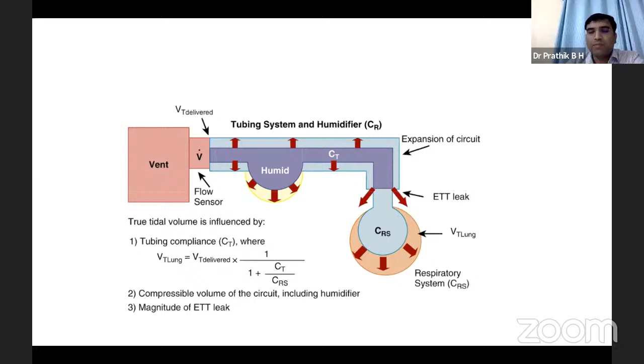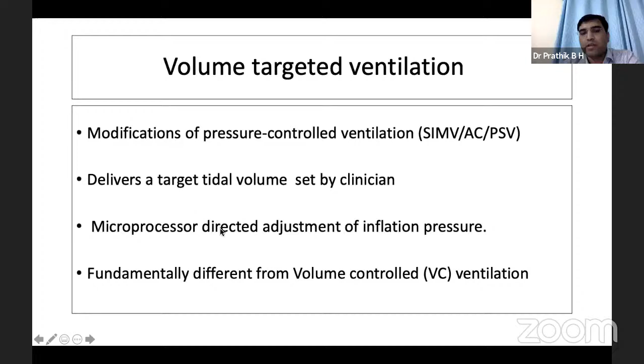So to overcome this problem, clinicians came up with what we call volume targeted ventilation. Basically, volume targeted ventilation is actually a modification of pressure controlled ventilation. The common pressure controlled ventilation modes which we use are SIMV, assist control, and also the PSV mode. Here in volume targeted ventilation, there is a delivery of targeted tidal volume, which is set by the clinician, based on the microprocessor adjustment of the inflation pressure. Let us see the steps of volume guarantee.